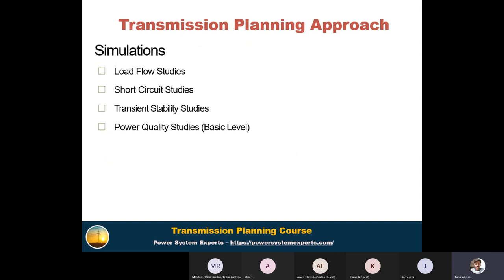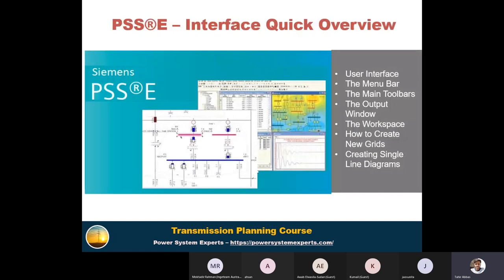Similarly, after that, we directly move towards the simulation. In simulation, we perform a load flow study and see whether, with the addition of this transmission line, the transmission losses are reduced and the voltage profile is improved. Similarly, we perform short circuit studies to check the breaker ratings, because with the addition of generation capacity in the future, definitely the fault level will increase. With transient stability, we see the stability of the system, and also the power quality studies. But at transmission level, we don't see power quality studies. We see power quality studies only at the distribution level, where the voltage variations are large. Okay, this is the PSS/E interface quick overview.